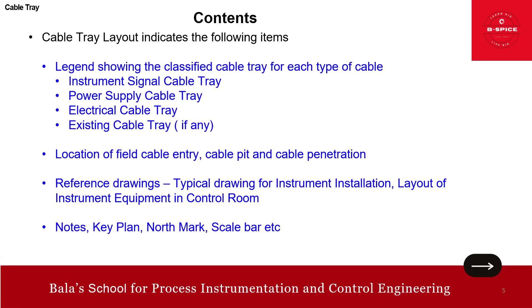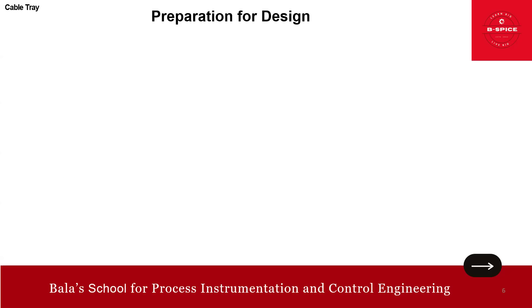One important suggestion: the instrument panel location layout drawing is the base drawing for preparation of MCT and for preparation of the cable tray layout. We should use that as the base information. Also, work demarcation should be part of this cable tray layout.